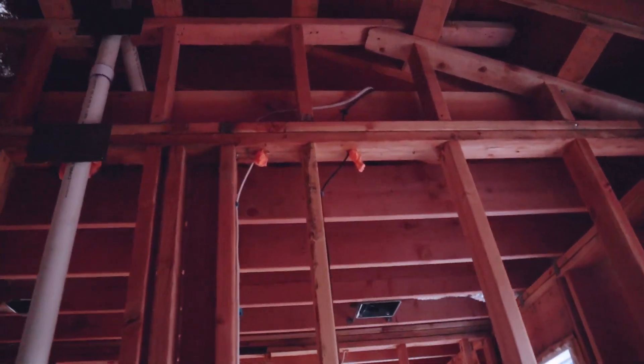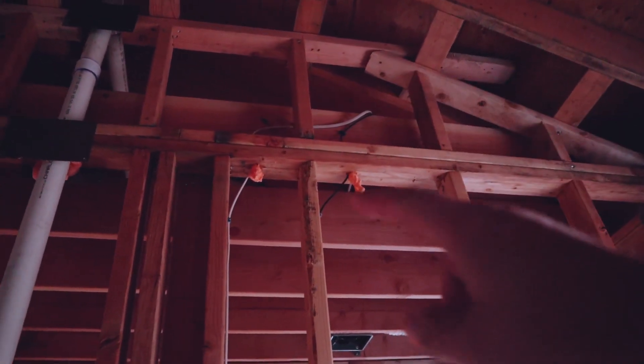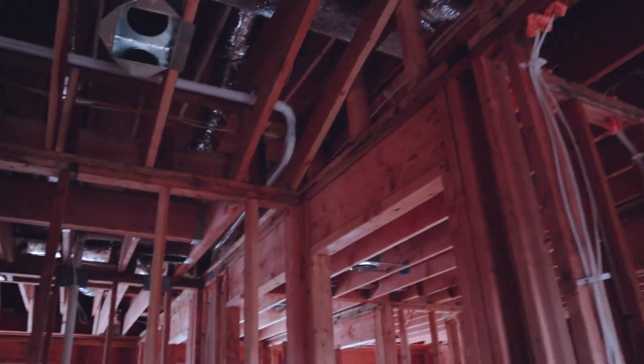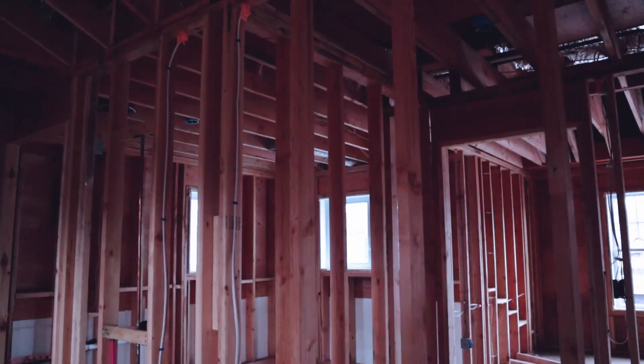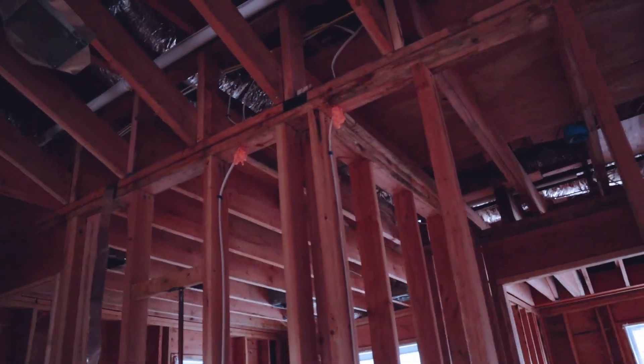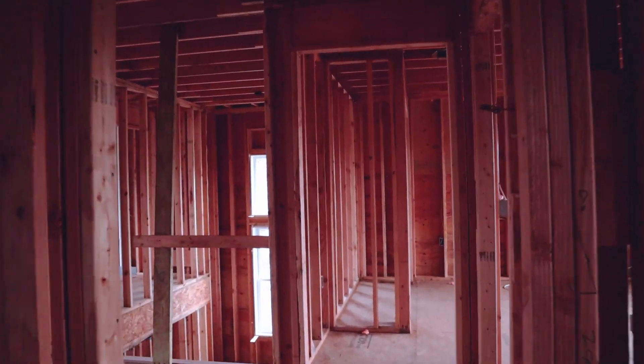Now this is what I'm here for today — this is the fire stop. The insulation company comes and puts this fire-rated insulation throughout all the holes in the framing, and that's part of what the inspector is going to be looking at. You can see the orange here. You also put it around all of the windows and doors as well. It's a fire preventative measure — basically not allowing, God forbid there was a fire inside, it wouldn't be able to get through these holes around the entire framing of the property, to confine the fire as much as possible.